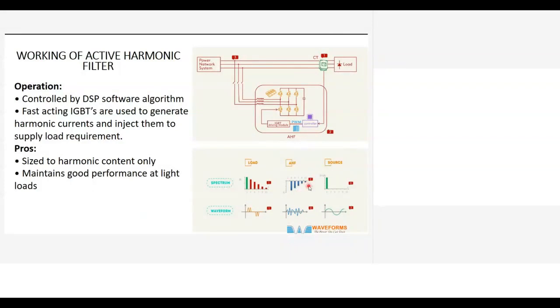So the total harmonics is measured at, say, the PCC, and normally this is installed at the MB panel. So it does mitigate harmonics closer to the MB panel and the transformer. But the harmonics inside the plant are not mitigated. They still remain inside the plant, and these harmonics will flow to the other nodes, and the adverse effects or ill effects of the harmonics will continue to be there inside the plant.